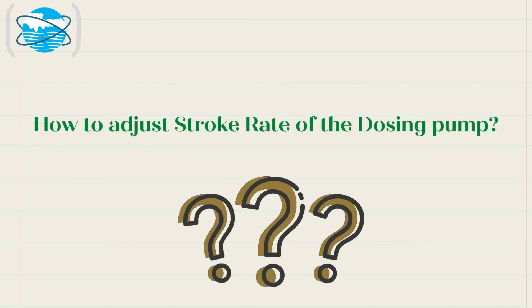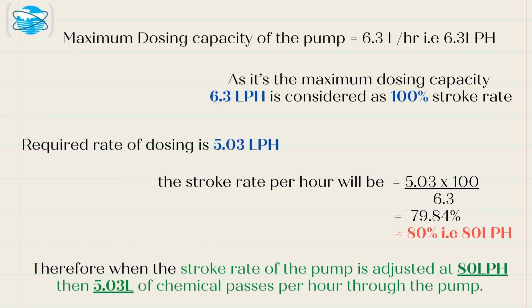How to adjust stroke rate of the dosing pump: if the maximum dosing capacity of the pump is 6.3 liters per hour, that is 6.3 LPH, then 6.3 LPH is considered as 100% stroke rate. As our required dosing is 5.03 liters per hour, the stroke rate per hour will be set to 80%. That means when the stroke rate of the pump is adjusted at 80%, then 5.03 liters of chemical passes per hour through the pump.